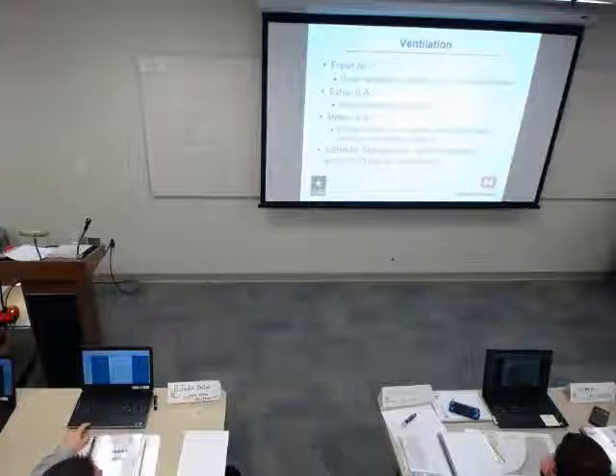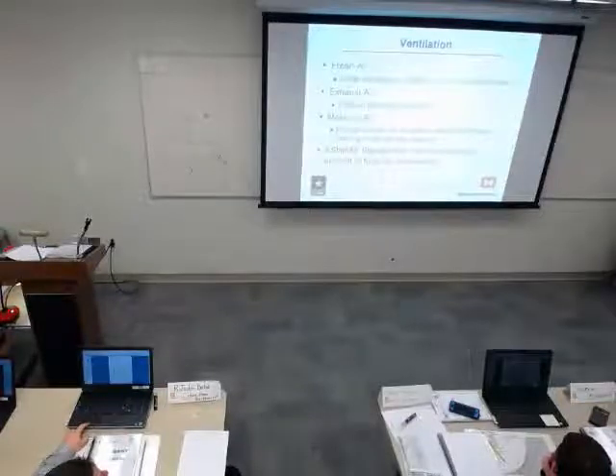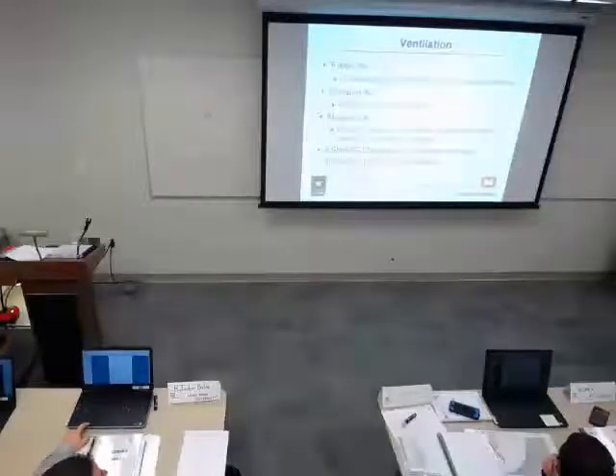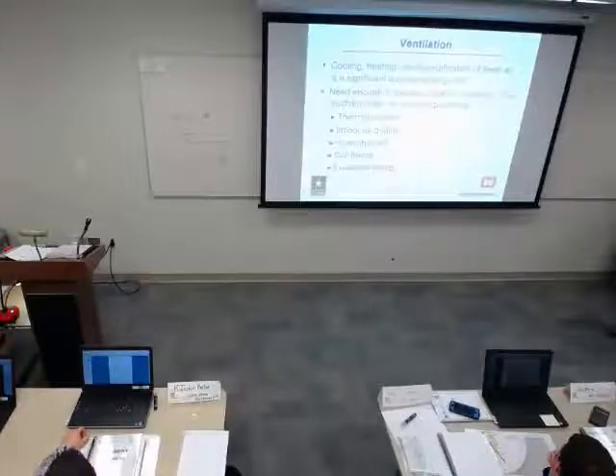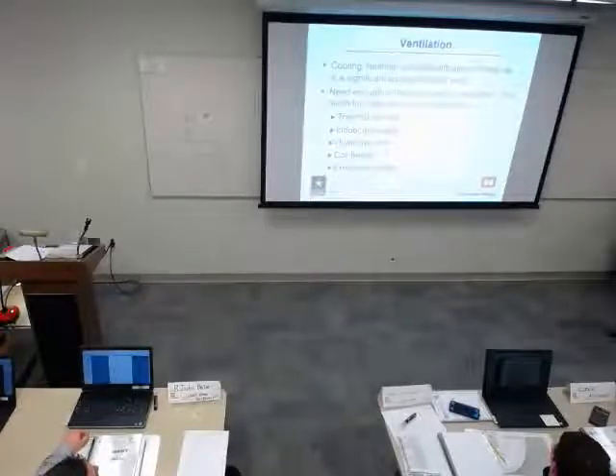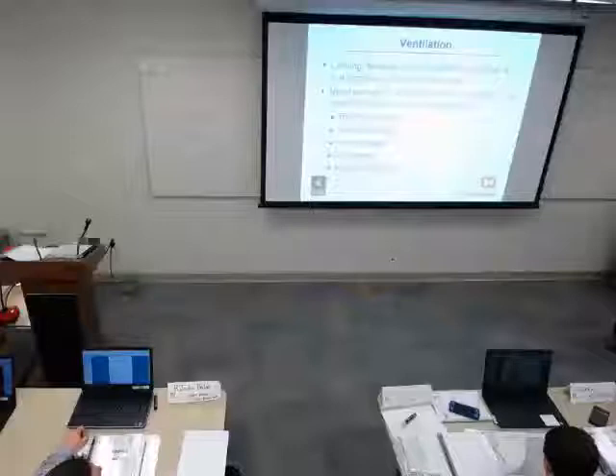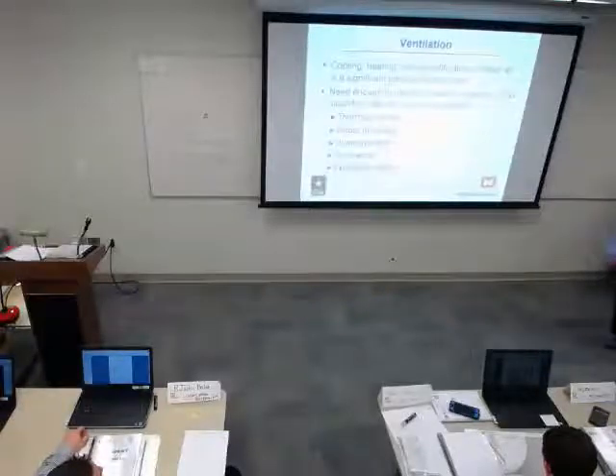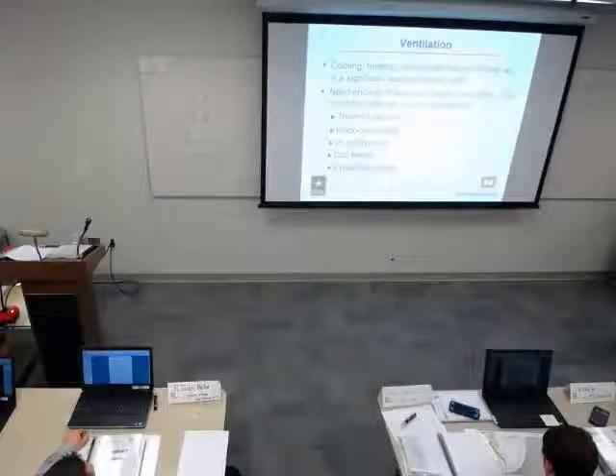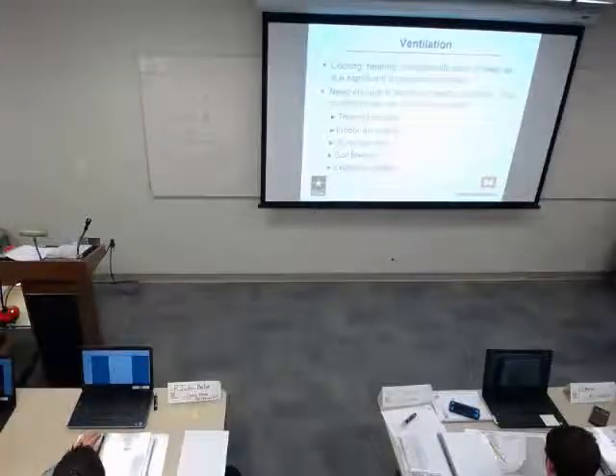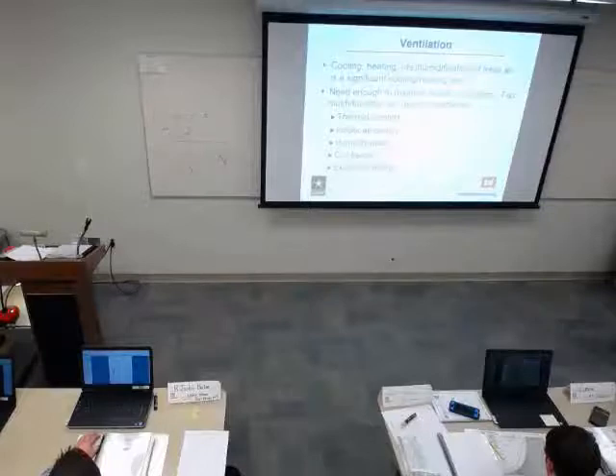ASHRAE 62.1 defines the required amount of fresh air and exhaust. And just to note, a term that doesn't show up except in the appendix in 62.1 is relief. Because in ASHRAE 62.1, all the air that's taken out of the building is called exhaust, and they don't really care where it comes from. In cooling and heating, the humidification of fresh air turns out to be a very significant load. One of the bigger components of that, in a good deal of the country, is the moisture in the air. We're going to need enough to maintain a healthy condition. Too much or too little gives us problems. We can have thermal comfort problems, indoor air quality problems, humidity, mold, and that very often is associated with leakage into the building. And then coil freeze-up and excessive consumption of energy.